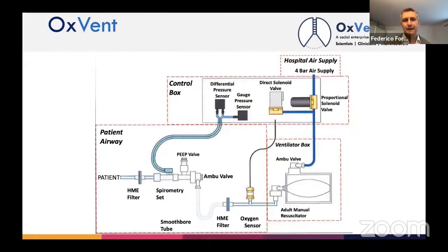By then, there was an improvement, a change in the design in terms of how the components were put together. We've seen that a core component called here the ventilator box, where there's this adult manual resuscitator, which instead of being operated by an individual's hand, is compressed by compressed air at 4 bar, the air supply, which is available in the NHS hospitals. And the air supply is controlled by solenoid valves. And there's an oxygen sensor here, as we can see, in this design to increase the fraction of inspired oxygen.